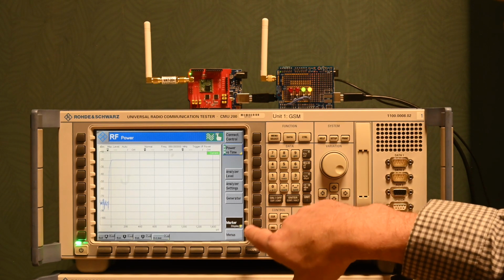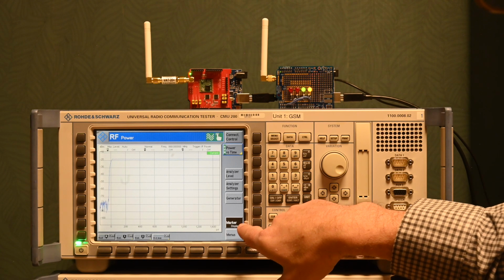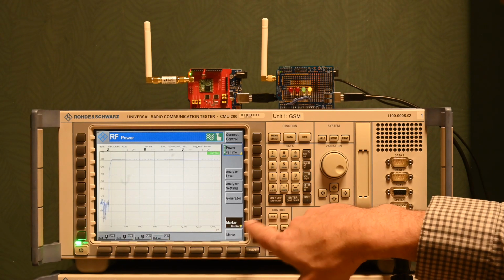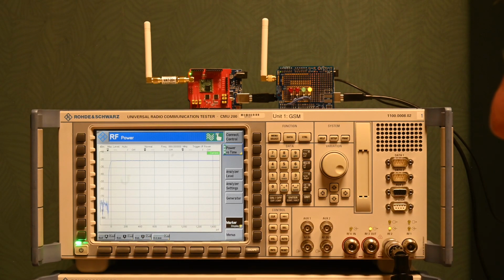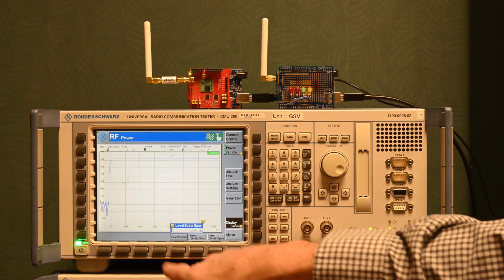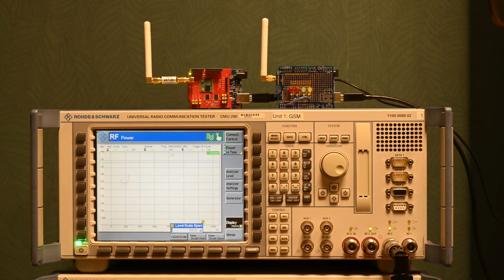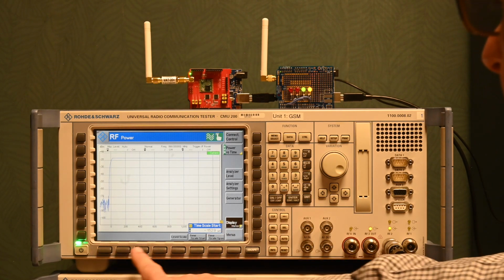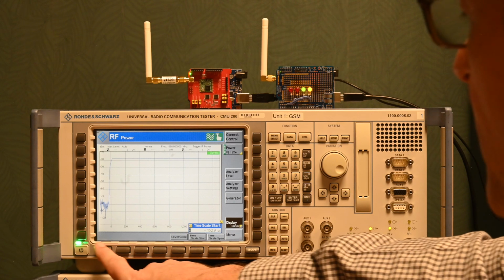the display menu, and if there's a little yellow thingy here, then that actually means there are two different menus here. So this is the regular marker menu. We'll look at that later when I'm going to investigate the spectrum analyzer. But we also have here the secondary menu, and that is actually time scale. So we got the level scale, so that is the vertical level, how many dBs. We got the time scale start, and this is the start relative here to the trigger point.